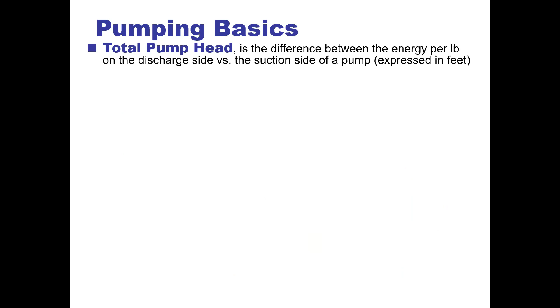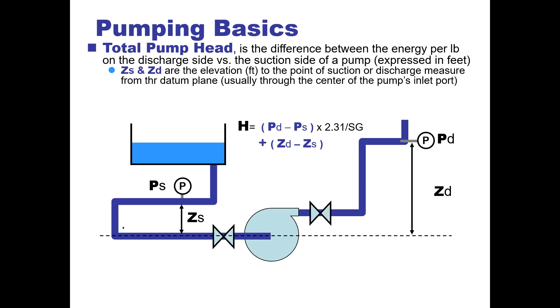Total pump head is the difference between the energy per pound on the discharge side versus the suction side of the pump, expressed in feet. So we're going to take the two points of measurement. ZD is the distance in discharge, ZS is our distance in suction. We're going to go right through the middle, the datum plane, or basically the middle of the eye or the suction side of our pump.